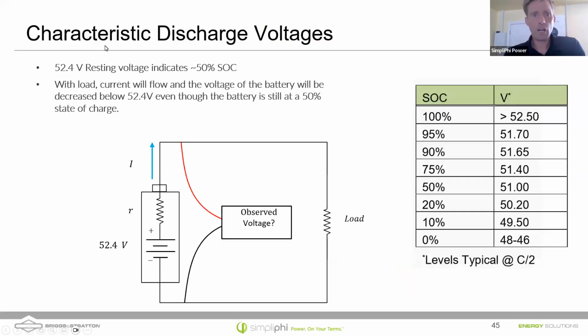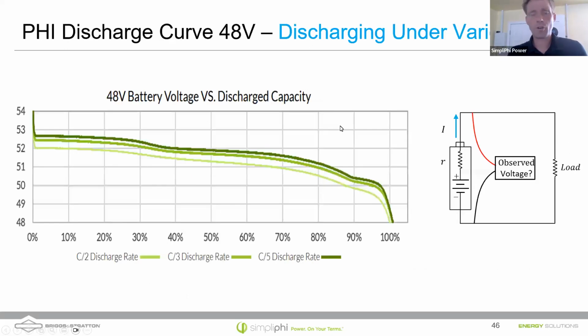So notice that these are the characteristics for discharge voltages. If I'm looking at 52.4 volts for a resting voltage, that's a 50% state of charge. When I'm discharging, I'm losing some voltage across the internal resistor, so there'll be a drop. Typically, this drop is about a couple of volts during a very fast discharge, like a C/2 discharge cycle. So keep that in mind. I'm going to show you what a curve looks like for different discharge rates.